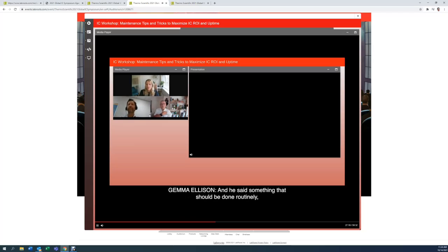Absolutely. And is this something that should be done routinely, not just when there's a problem? Should we be checking test conditions on a regular basis? Well, I think every time you run your chromatograph, you'll be doing a standard of some description, maybe a mid-range standard. Something that I used to do while I was an engineer. I used to be running what we called a query within 7.3. It's called something different now, and you can query that one chromatogram for the lifetime of the instrument on that data vault, and then you can trend those results as they came through.